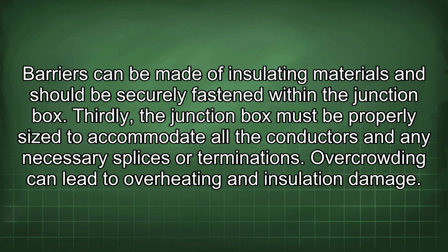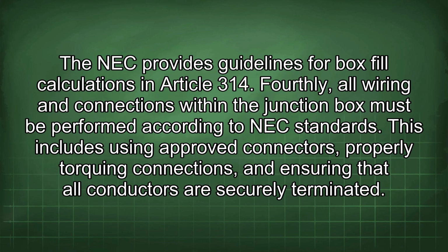Thirdly, the junction box must be properly sized to accommodate all the conductors and any necessary splices or terminations. Overcrowding can lead to overheating and insulation damage. The NEC provides guidelines for box fill calculations in Article 314. Fourthly, all wiring and connections within the junction box must be performed according to NEC standards. This includes using approved connectors, properly torquing connections, and ensuring that all conductors are securely terminated.